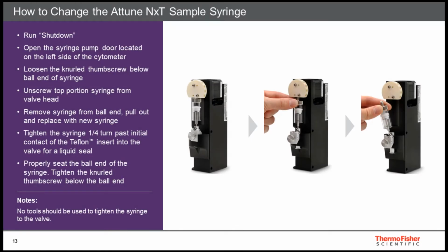To change the syringe, ensure the system is completely powered off, ideally after running the Shutdown or Decontamination script. In order to change the syringe, open the side door, loosen the thumb screw below on the plunger end of the syringe. The goal here is to loosen and not completely take off. Tools may be required to loosen the screw. Unscrew the top portion of the syringe just using your fingers. The glass portion of the syringe may shatter if mishandled.